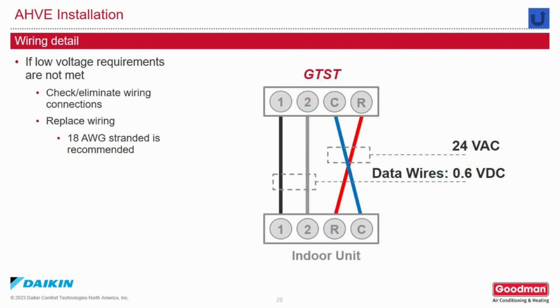If low voltage requirements are not met, check or eliminate wiring connections. Replace the wiring. 18 gauge stranded is recommended, particularly on the communication circuit. The red and common can be solid core since it's only carrying 24 volts AC.